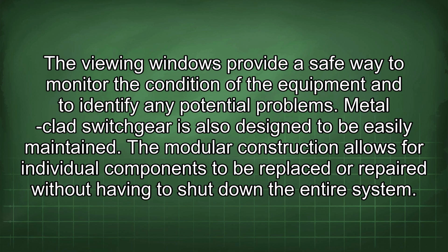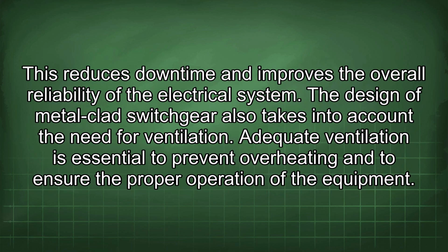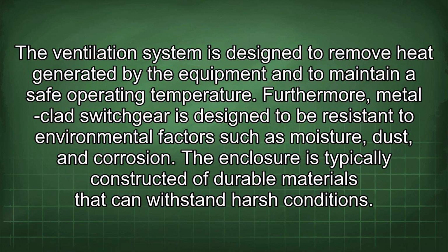The modular construction allows for individual components to be replaced or repaired without having to shut down the entire system. This reduces downtime and improves the overall reliability of the electrical system. The design of metal-clad switchgear also takes into account the need for ventilation. Adequate ventilation is essential to prevent overheating and to ensure the proper operation of the equipment. The ventilation system is designed to remove heat generated by the equipment and to maintain a safe operating temperature.